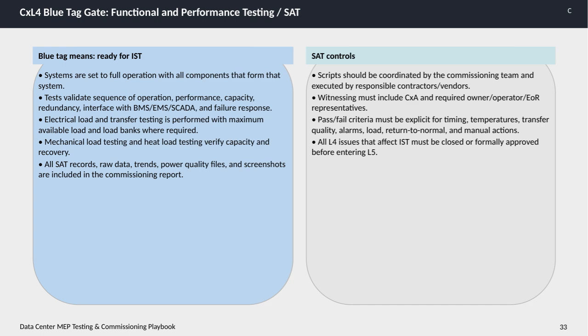Similarly, mechanical load testing and heat load testing are performed to confirm the system's capacity and its ability to recover properly. It's important to note that all data gathered during these tests, including raw data, trends, power quality files, screenshots, and detailed site acceptance testing records, are included in the final commissioning report. This ensures transparency and provides a solid baseline for system performance.